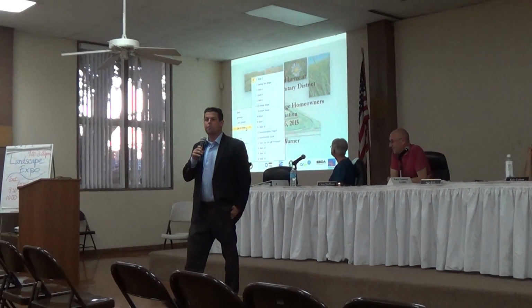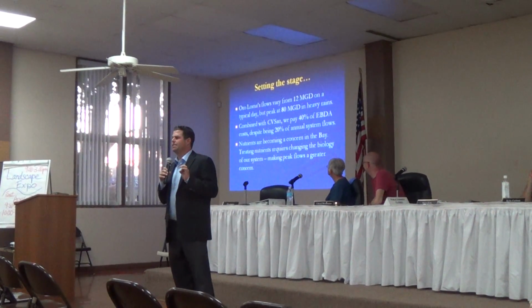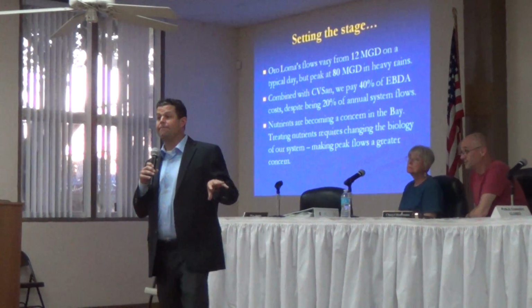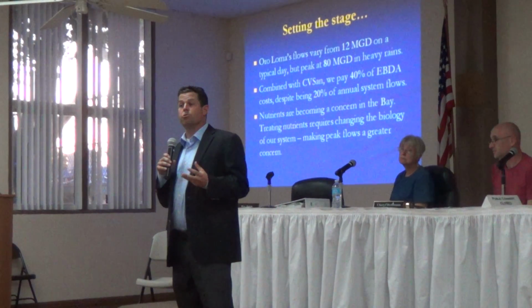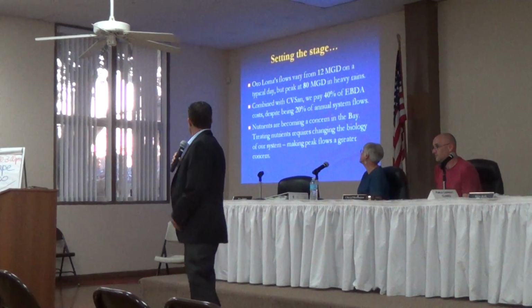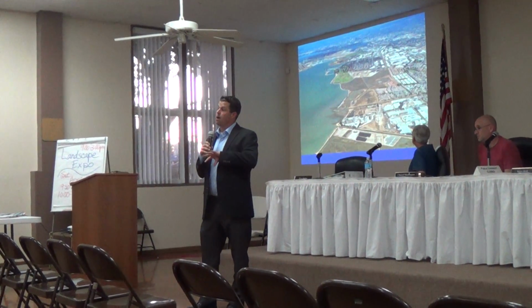Basically Oro Loma's facing a couple different things. I think a lot of things are going right at Oro Loma. Historically, one of our Achilles heels has been high peaking flows compared to average flows. When it rains, lots of rainwater goes in and finds defects in the pipes and ends up at our plant. Where we might see about 12 million gallons per day in a regular day, we'll see 80 million gallons per day during a storm. This is something we've wanted to manage for a long time. The way other treatment plants manage this is they build a parking lot for that extra flow. They hold it, wait for the rain to go by, and then bring that flow back into the plant.